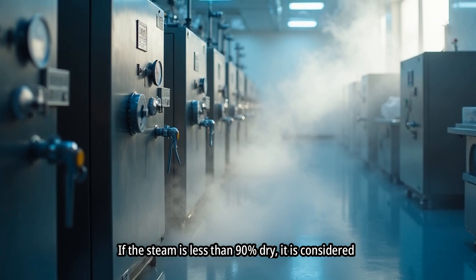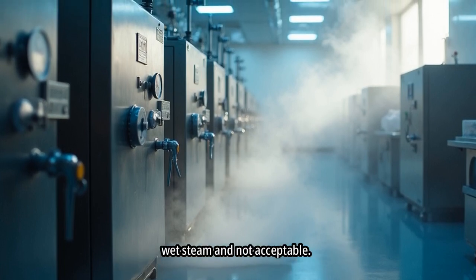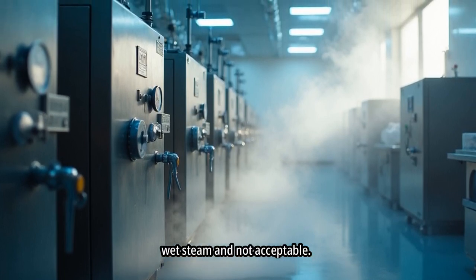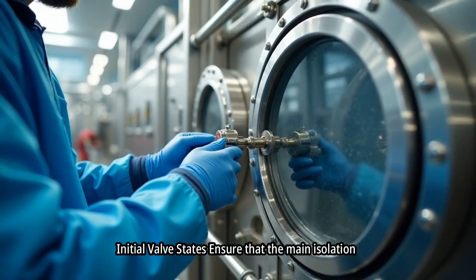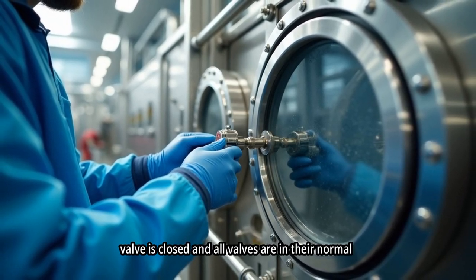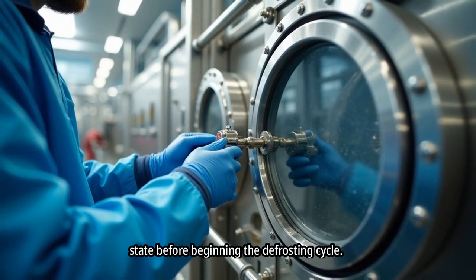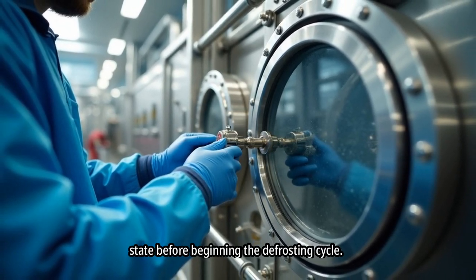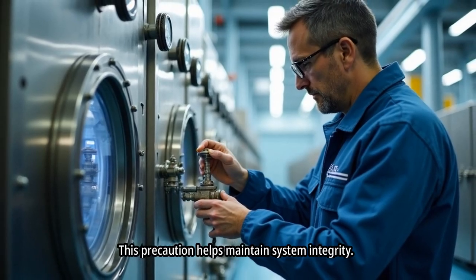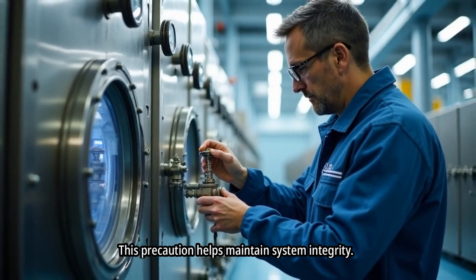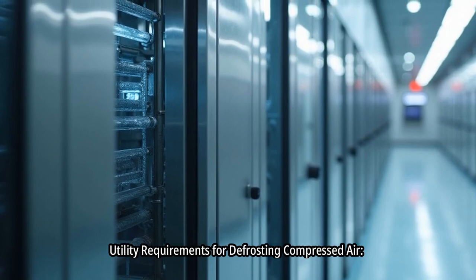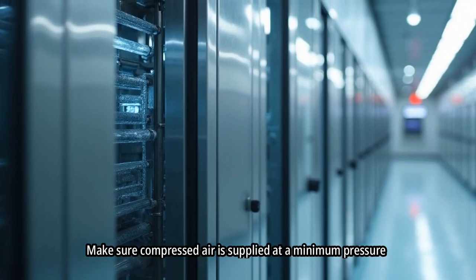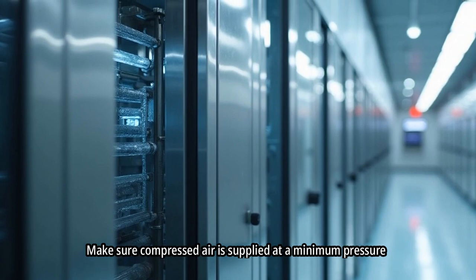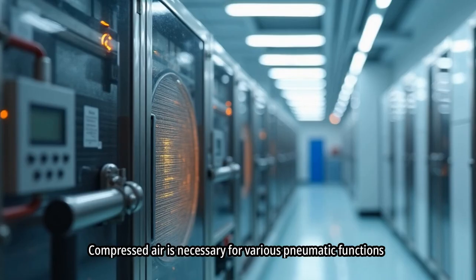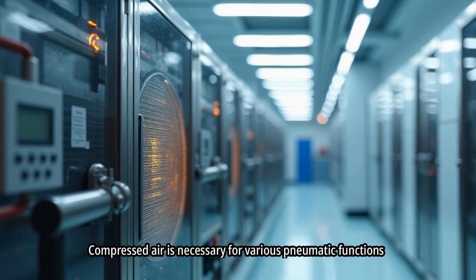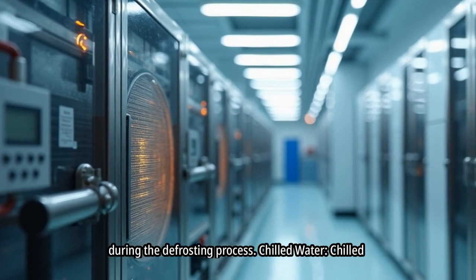If the steam is less than 90% dry, it is considered wet steam and not acceptable. Initial valve states ensure that the main isolation valve is closed and all valves are in their normal state before beginning the defrosting cycle. This precaution helps maintain system integrity. Utility requirements for defrosting: compressed air. Make sure compressed air is supplied at a minimum pressure of 0.4 MPa. Compressed air is necessary for various pneumatic functions during the defrosting process.